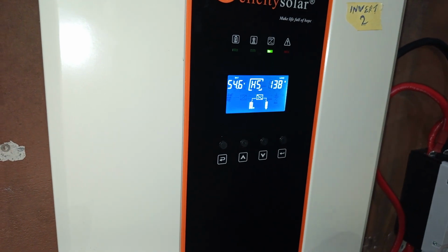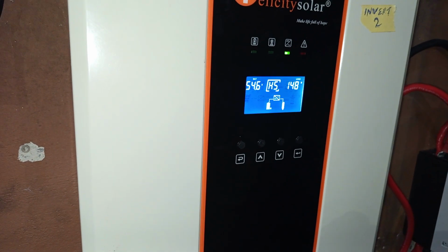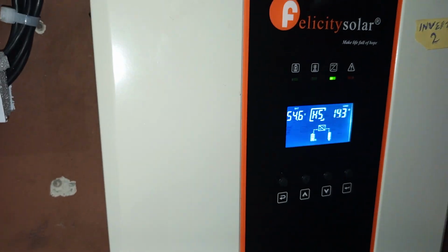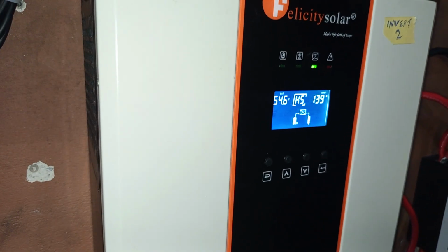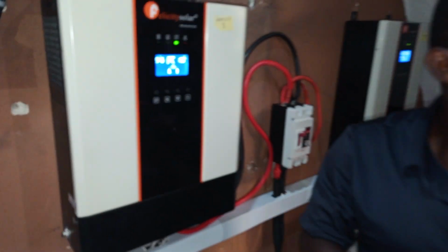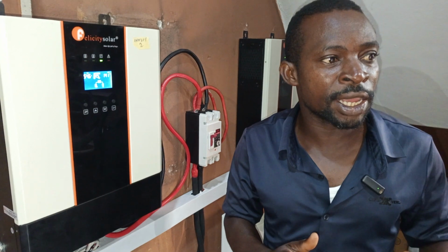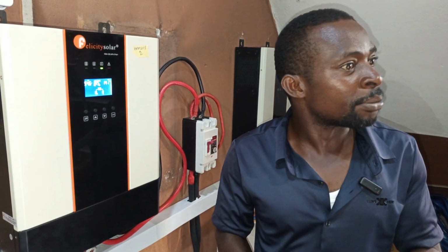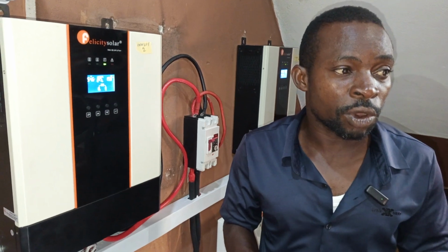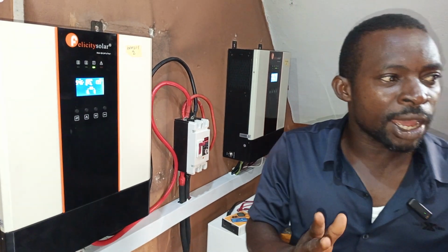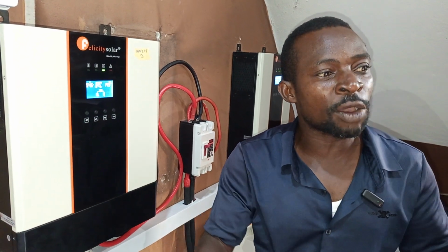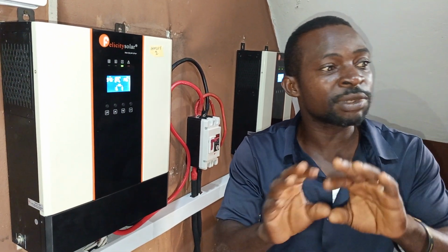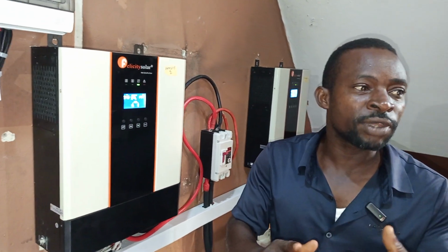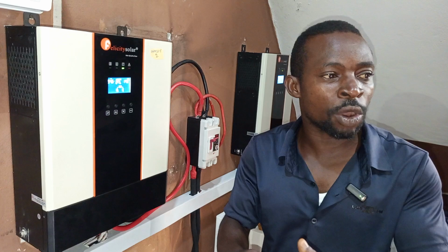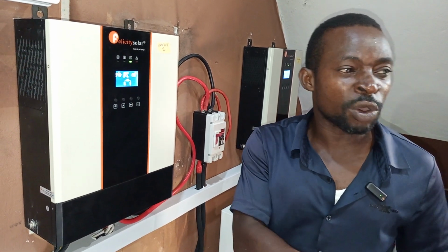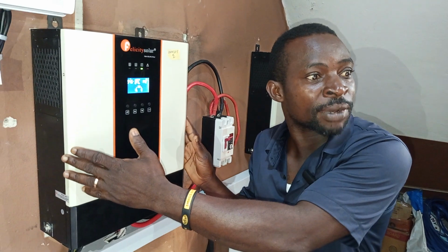You can see they share the load equally. If you have one single 10 kVA unit and something happens, your inverter goes bad, you'll stay without light all year. But with two units you can manage one while we fix the other. There's a lot of advantage to this setup. In some countries they tie all their connectivity to the grid, so if one engine room fails, others keep working while they fix that equipment. The same principle applies to this installation.